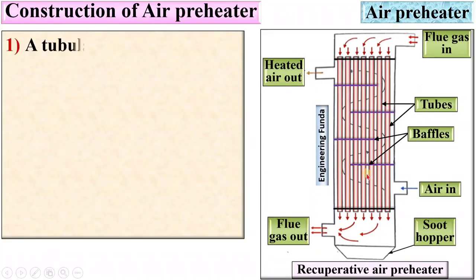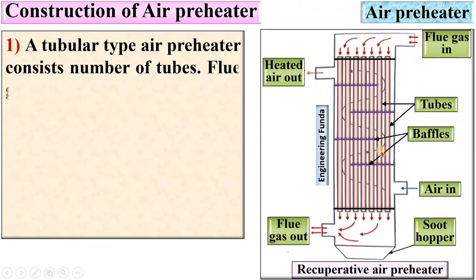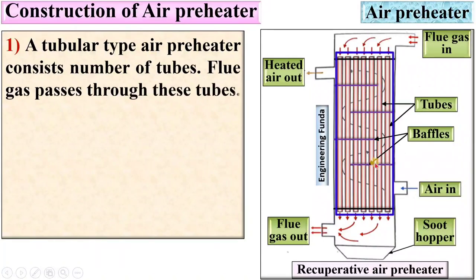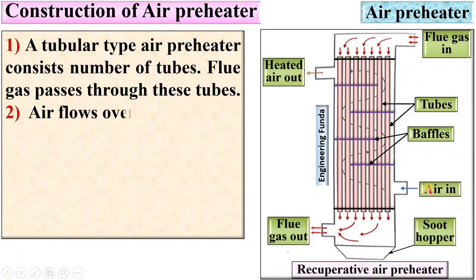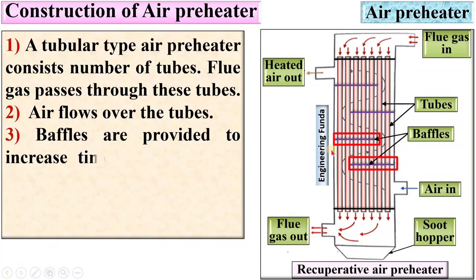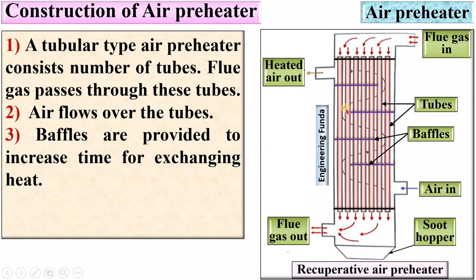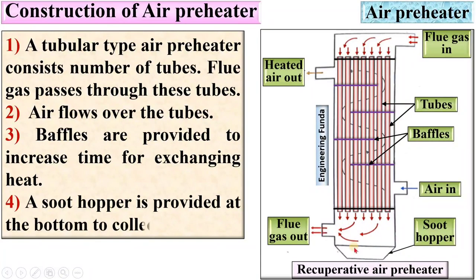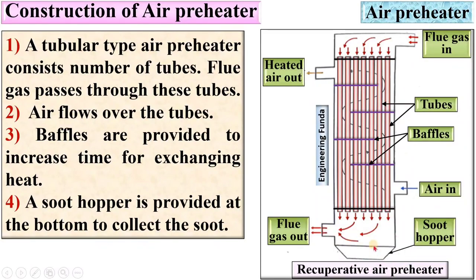Construction of the air preheater: a tubular type air preheater consists of tubes. Flue gases pass through these tubes, and air flows over the surface of these tubes. Baffles are provided to increase the time for exchanging heat from the flue gases to the air. A soot hopper is provided at the bottom of the air preheater to collect the soot or dust.